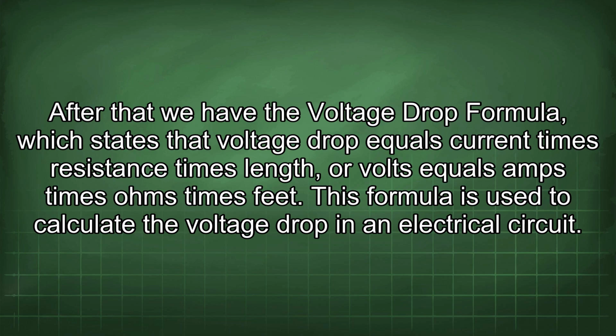After that, we have the voltage drop formula, which states that voltage drop equals current times resistance times length, or volts equals amps times ohms times feet. This formula is used to calculate the voltage drop in an electrical circuit.